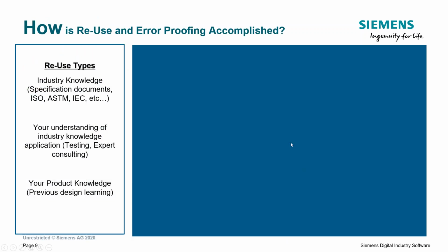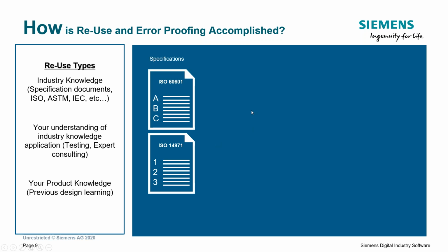Okay, so I'm going to just talk for a few minutes about reuse and how to construct a library system that would allow you to reuse these artifacts and provide traceability into your standards. And so this construction, we're going to start with specifications, which are really external standards. And so you might think in terms of 60601, which is requirements for electrical medical devices. Another example might be 62304, which is software for medical devices, right? So we have these external standards, and the external standards update on a cadence that we don't really control. So we might have 60601 2007, and then at some point in time they update to 2012. And so we don't really control the update of those documents. They occur at a cadence that we don't control, as I said a minute ago. So we have a library that keeps track of those. What is it that the external standards require?